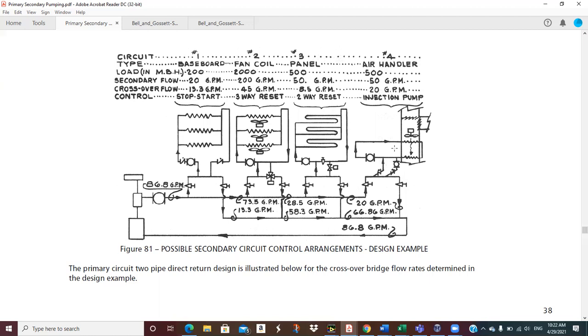Oh, he's also showing you the various flow rates that you would use for pipe sizing, because when you start out, you're pipe sizing for 86.8, but once you get up to this point, we're pulling 13.3. So in this pipe, I've only got 73.5 GPM. And that looks like a short pipe, but that could be 100 feet before you get down to the next one in a real building. And so that pipe would potentially, that's not a lot. It may or may not be downsized, but then we're going to pull out 45 GPM. So now we're down to 28.5. So I guarantee you this pipe size is going to be smaller as we come on down through here. And then from this point, we only got 20 GPM around here, 20 GPM there.